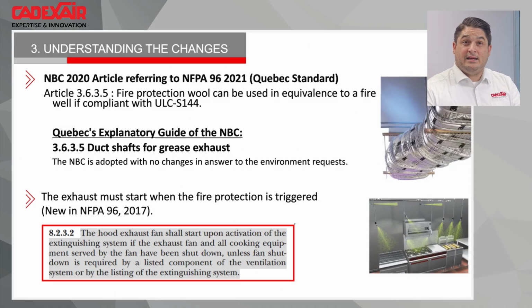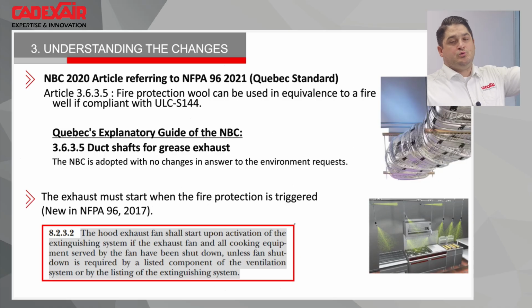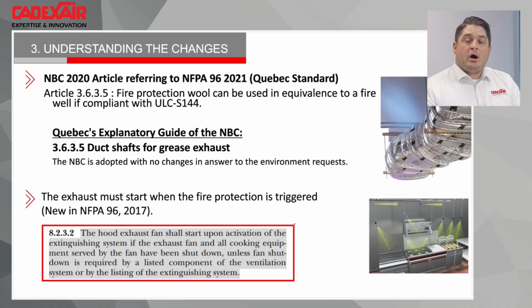Maybe another point that has been requested, and that could be a little problem, because as soon as you get a fire, normally you shut down every fan that exists. But now in NFPA 96, they will ask you to start the fan as soon as the fire protection system is activated. From my point of view, the main reason is they will use the fan to draw up the fire extinguishing liquid from the system that will rise through the ductwork. So that's why they request that.